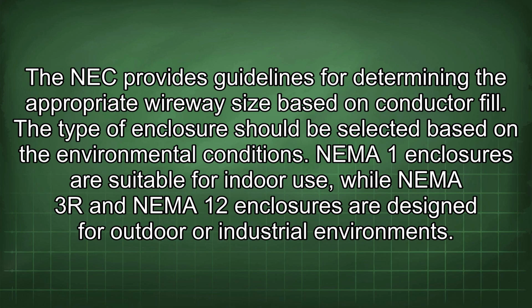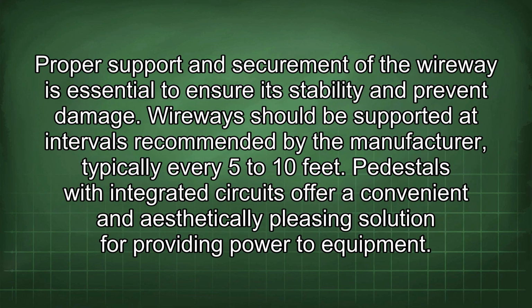The type of enclosure should be selected based on the environmental conditions. NEMA 1 enclosures are suitable for indoor use, while NEMA 3R and NEMA 12 enclosures are designed for outdoor or industrial environments. Proper support and securement of the wireway is essential to ensure its stability and prevent damage. Wireways should be supported at intervals recommended by the manufacturer, typically every 5 to 10 feet.